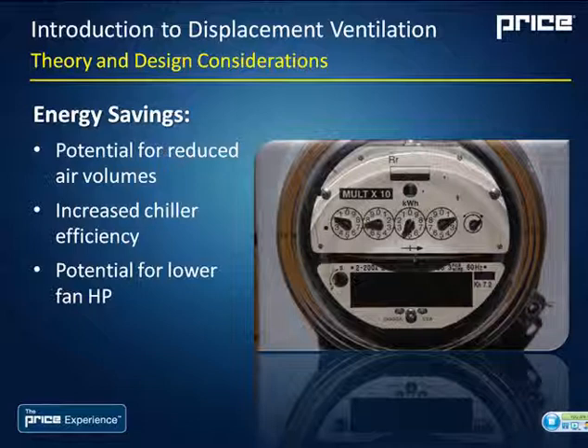So the air volume above that doesn't really need to be conditioned. And you can actually see a reduction in air volumes required to cool the room. This can be more significant if you're looking at something like a theater with very intense stage lighting. The convective load associated with all of that lighting is really not attributed to the occupied zone only, and you're just concerned about the radiant portion that falls into the occupied zone. So there's a significant portion there that really doesn't need to be conditioned. It can just stratify and be pulled out by the returns.